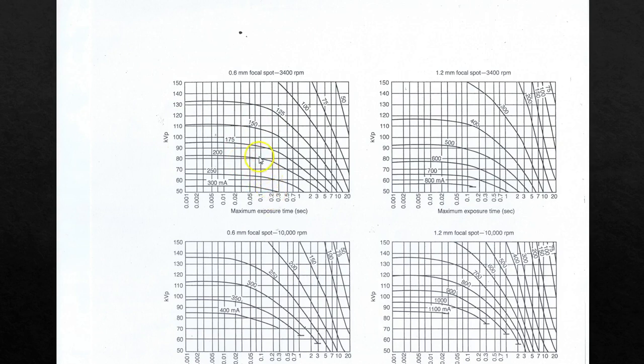If I'm choosing 150 MA and 100 KVP and 0.1 second, is that going to be safe or unsafe? Here's my 100 KVP line — go over to 0.1 second, and it is below the 150 curve. Totally safe. But if I dial that up to 200 MA — unsafe. The computer is probably not going to let me do it.